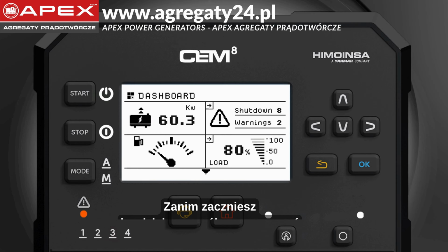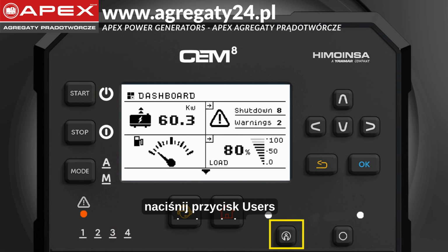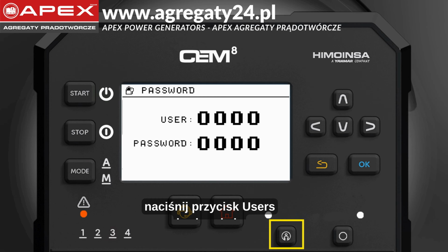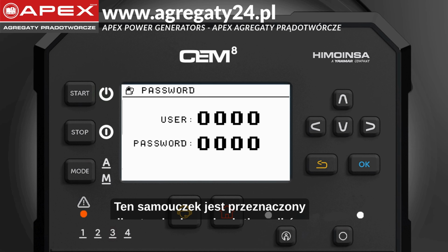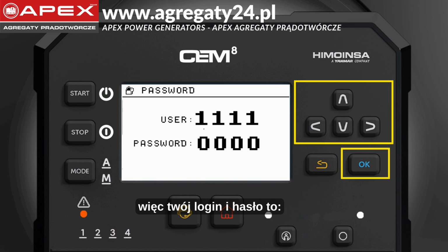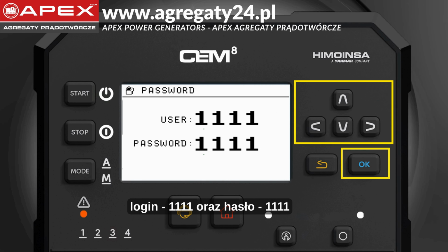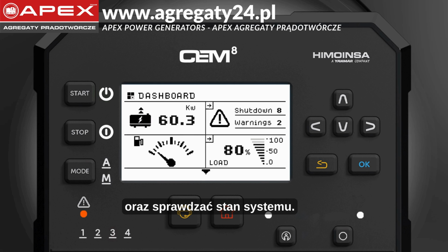Before you interact deeply with the controller, press the Users button and log in with your profile. The controller uses a user system that defines different access levels, and each profile has different permissions to operate or configure the system. This tutorial targets standard users, so your access is user 1111 and password 1111. This level allows you to start and stop the generator, view electrical parameters, and check system status, among other functions.